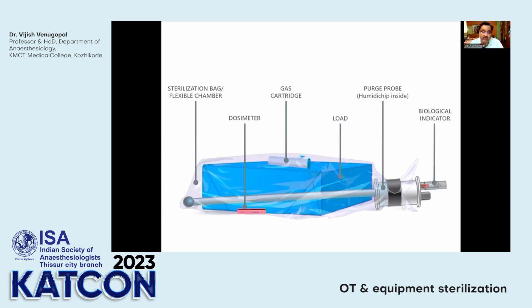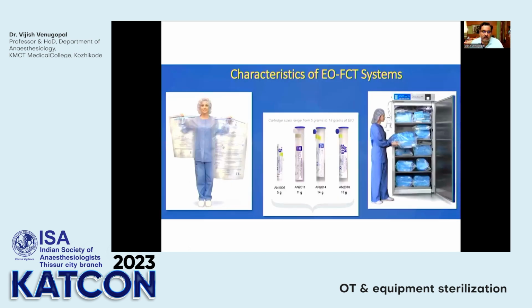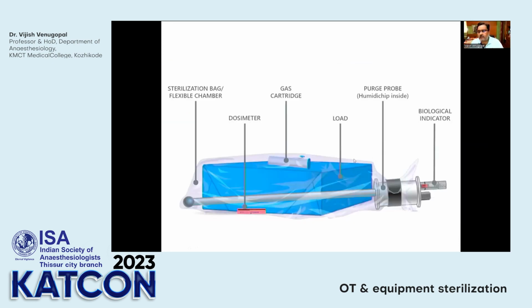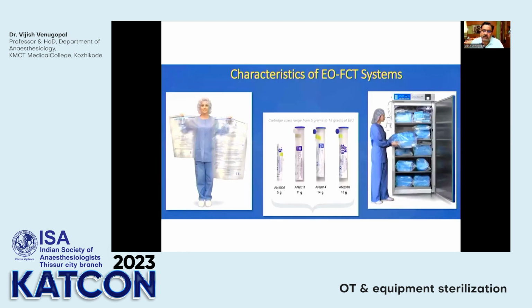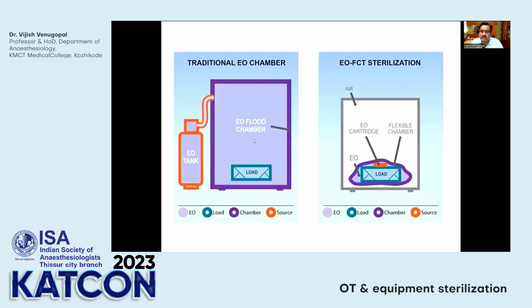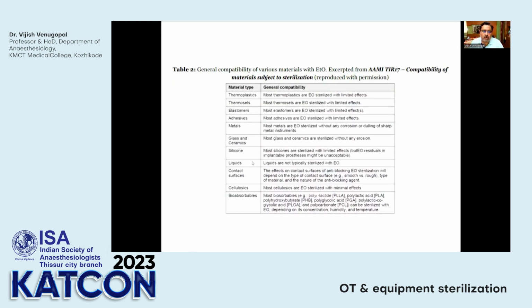But now there are some advancements like the flexible chamber, where you have different size bags, and you can put in the instruments, and then you can put a very small amount of 5 to 18 grams of ETO in as a cartridge inside, and vacuum is applied, and you initiate the ETO sterilization. And there you can put in a purge probe also, which can evacuate the ETO at the end of the cycle. So the advantages are that it doesn't require such a big space, and the ETO used is very minimal, and almost all objects can be sterilized with ETO except for the liquids. Liquids cannot be sterilized with ETO.